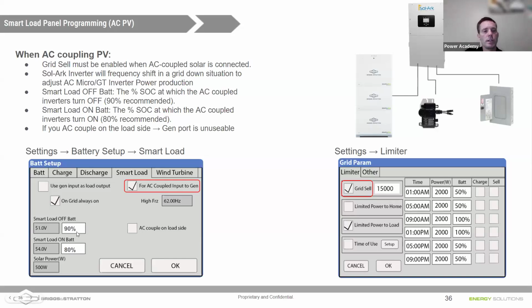And then there's a discrepancy between what turns it back on and what turns it off. We're going to let those batteries discharge a little bit before we turn it back on. And so that's why we're down at 80% before we turn the AC coupled solar back on in a grid down event. And that prevents this rapid on-off cycling. Daniel, do we have any questions coming? Yeah, I think I remember looking at this, and what it's saying is anytime the battery is below 80%, the AC coupled solar is on. Yes. Anytime it goes above 90%, it's going to shut off, right? So it has to drop that 10%. With a qualifier in a grid down situation.